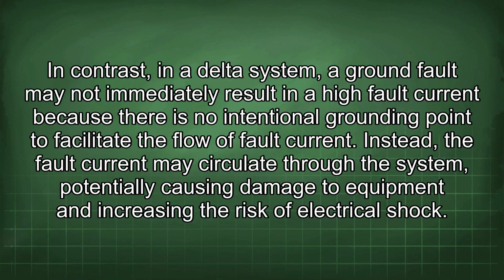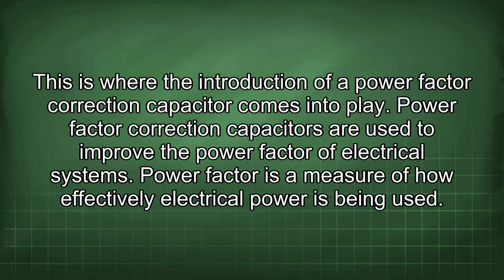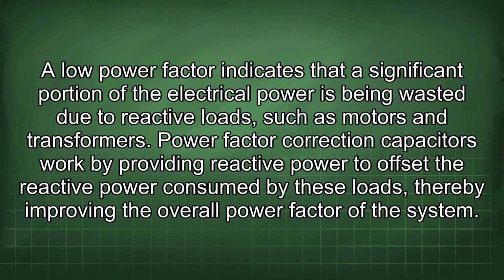In contrast, in a delta system, a ground fault may not immediately result in a high fault current because there is no intentional grounding point to facilitate the flow of fault current. Instead, the fault current may circulate through the system, potentially causing damage to equipment and increasing the risk of electrical shock. This is where the introduction of a power factor correction capacitor comes into play. Power factor correction capacitors are used to improve the power factor of electrical systems. Power factor is a measure of how effectively electrical power is being used. A low power factor indicates that a significant portion of the electrical power is being wasted due to reactive loads such as motors and transformers. Power factor correction capacitors work by providing reactive power to offset the reactive power consumed by these loads, thereby improving the overall power factor of the system.